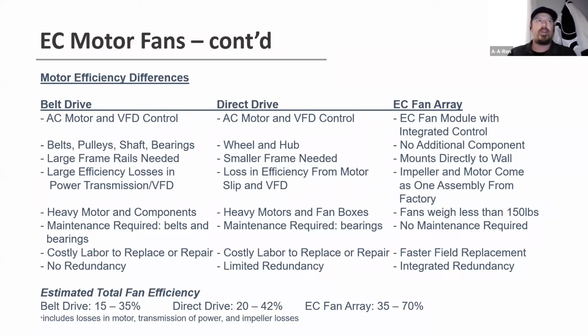So when we talk about EC fan arrays, I like to go over a lot of the differences between what you have in there currently and some other options from other competitors. When you're looking at belt drives, you always have VFDs. Even with direct drive systems, you have VFDs. And with ECs, we have the integrated electronics built onto the back of the motor. In essence, it acts like a VFD, but instead of changing the hertz profile, we do it controlled through DC link. We just voltage control the winding speed. So you still have full speed control for a 0 to 10 VDC. In essence, you can run these fans all the way down to like 10% of their max RPM, all the way to full speed without any additional heat load or anything like that.